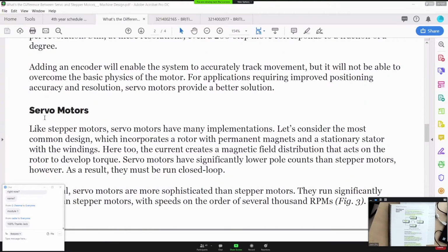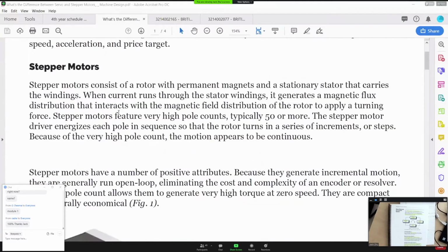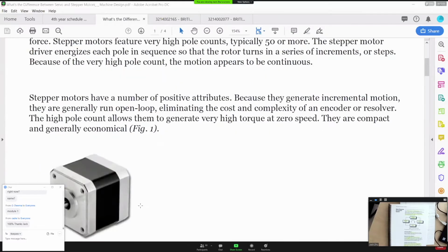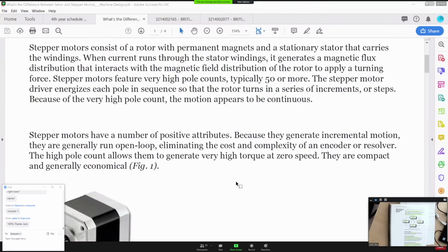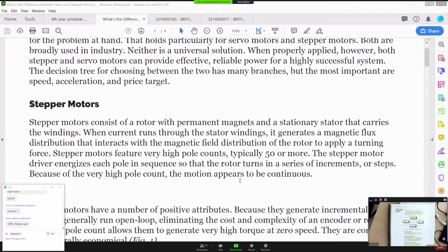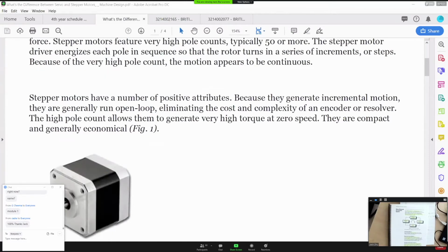So the step motor, they put a type of pulse into the motor control part, and the motor will turn. Basically, those are for position, location. So the motor will turn a certain degree. Internally, they have lots of magnetic poles, so they will energize those poles to make the motor turn to a certain degree. So that will move something to a certain location. But with this step motor, you put the signal in, they will move, there is no feedback. So there's no feedback to tell you how much the rotor moved.